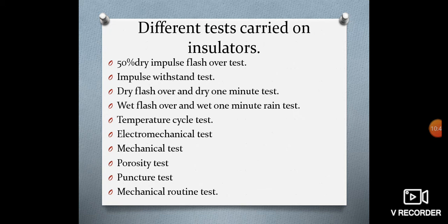Next is the puncture test. An impulse overvoltage is applied between the pin and the lead foil bound over the top and side grooves in case of pin type and post insulator, and between the metal fittings in case of suspension type insulators. The voltage is a 1 by 50 microsecond wave with amplitude twice the 50% impulse flashover voltage and negative polarity. 20 such applications are applied. The procedure is repeated for 3.5 times the 50% impulse flashover voltage and continued till the insulator is punctured. The insulator must not puncture if the voltage applied is equal to the one specified in the specifications.